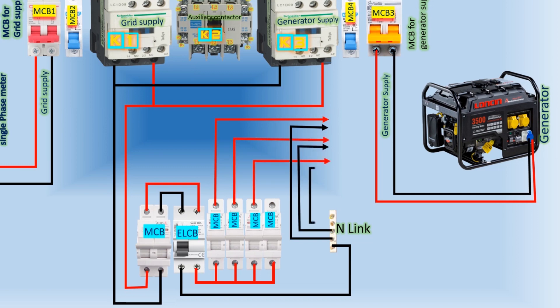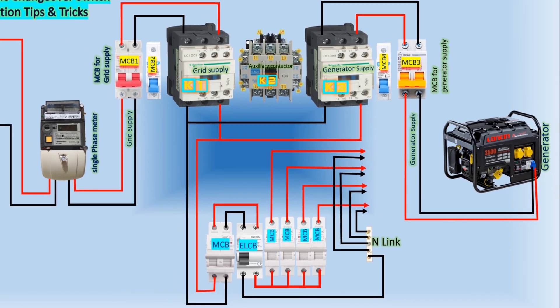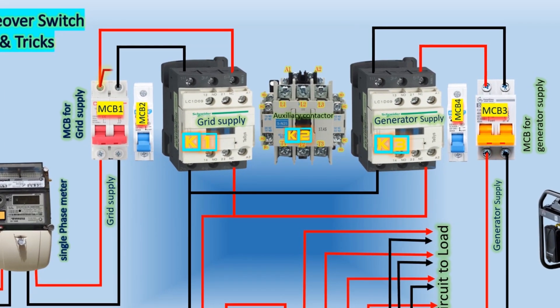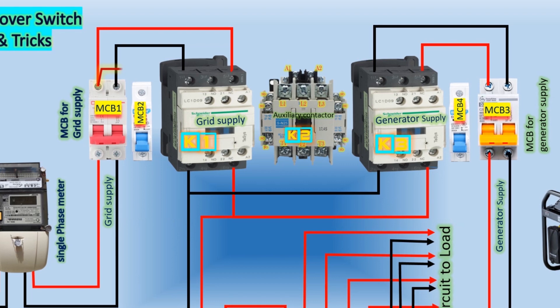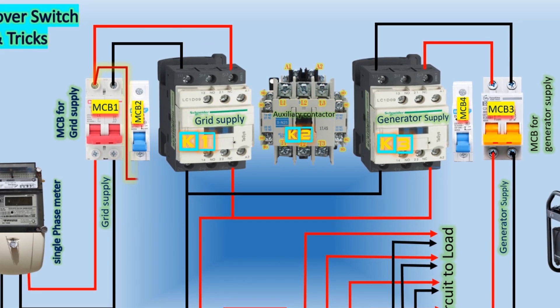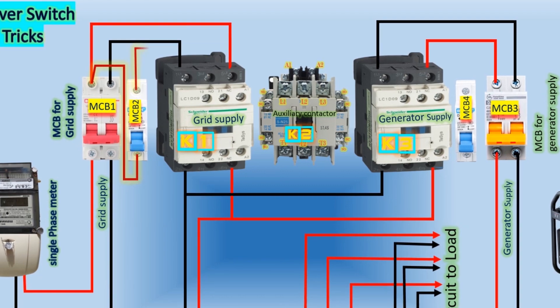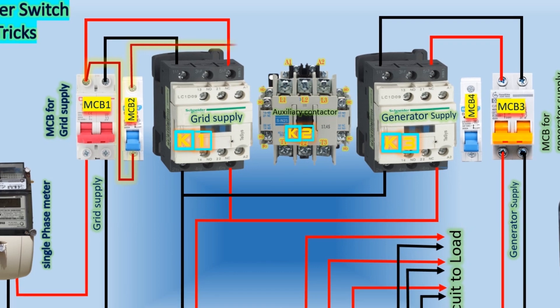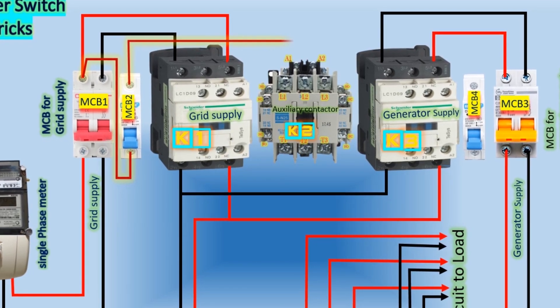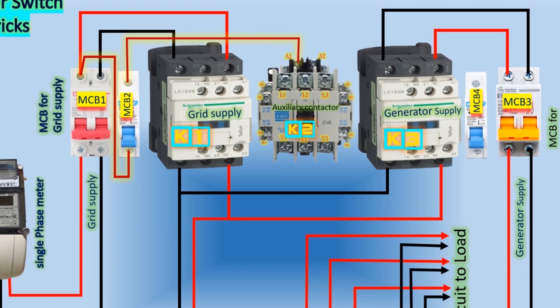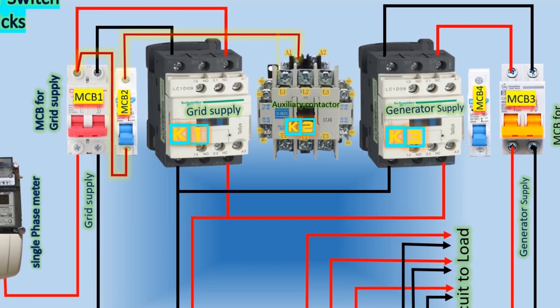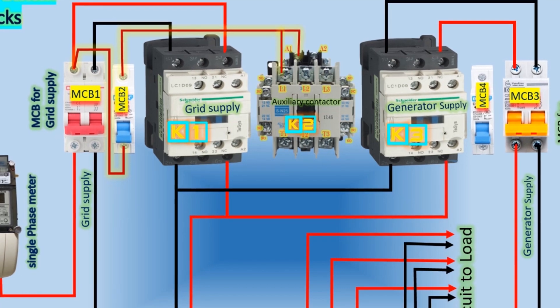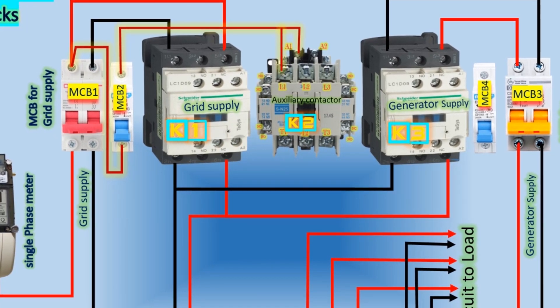Now, let's move on to the control circuit. A wire is taken from the output of two-pole MCB1's phase wire and connected to the single-pole MCB2. From the output of this single-pole MCB, a wire is directed to the coil terminal of the auxiliary contactor. This wire is also looped with the L1 terminal of the auxiliary contactor. Additionally, a neutral wire from the T1 terminal of the auxiliary contactor is connected to the A2 coil terminal of the auxiliary contactor.